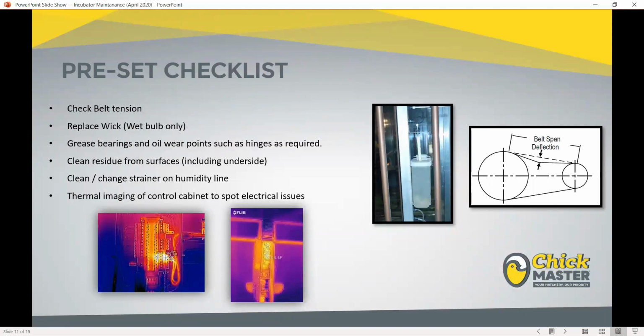Now, during this process, it's highly recommended that you get yourself some thermal imaging equipment. FLIR, which is a company we use extensively, offers some great pieces of equipment which can turn any smartphone into a thermal imaging piece of equipment. And this is great for spotting hotspots in control cabinets, which is a great early indicator of faults within a control cabinet. So if a contact is going or a relay starting to go, or you've got a loose cable which is starting to arc, the first indicator of that will be a hotspot in your control cabinet. And this is a great chance to spot it before it creates a breakdown in your machine.